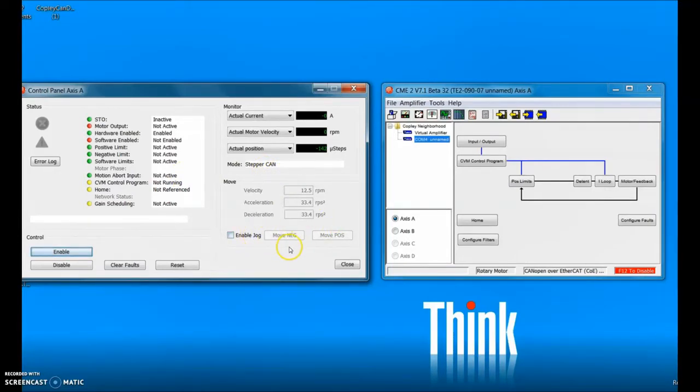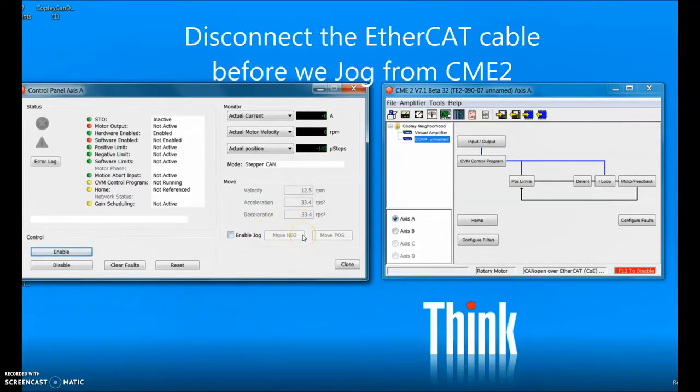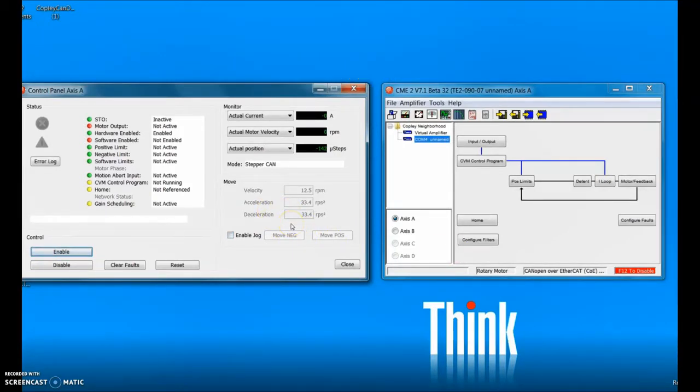When you enable it to CANopen over EtherCAT, be sure not to save it in a software program mode if you jog it. Another thing about jogging with the CANopen master: you should disconnect the CANopen master, because even if it's not running software there could be messages commanding position, which could jog positive and negative — so just disconnect the EtherCAT cable.